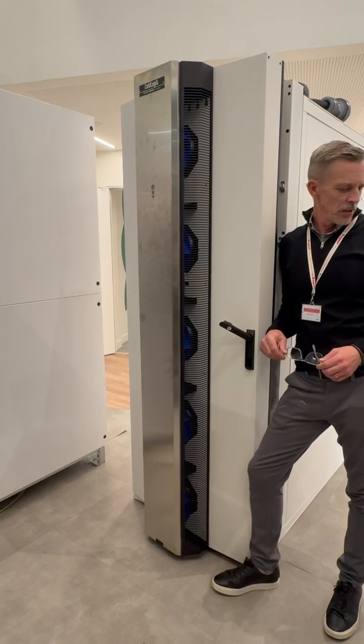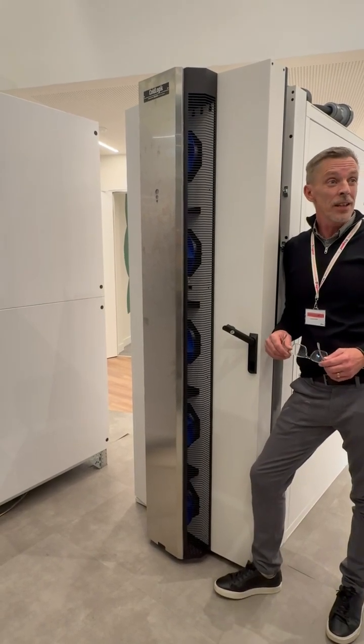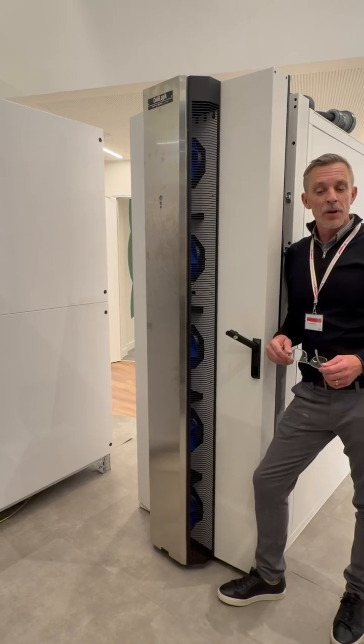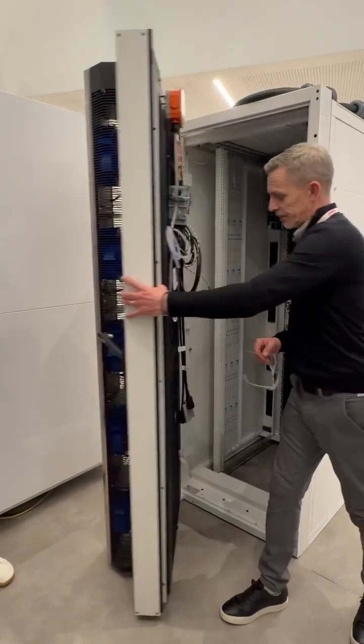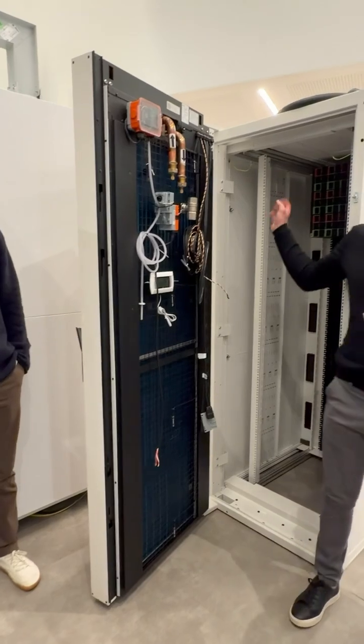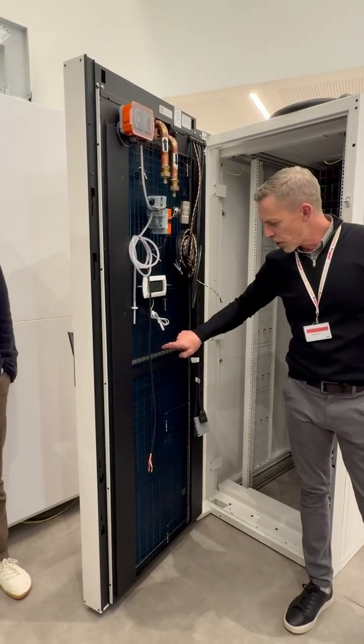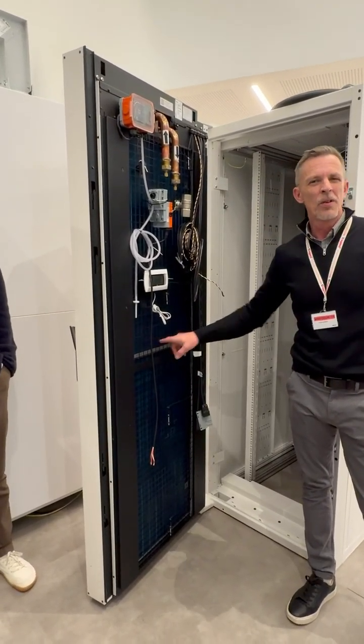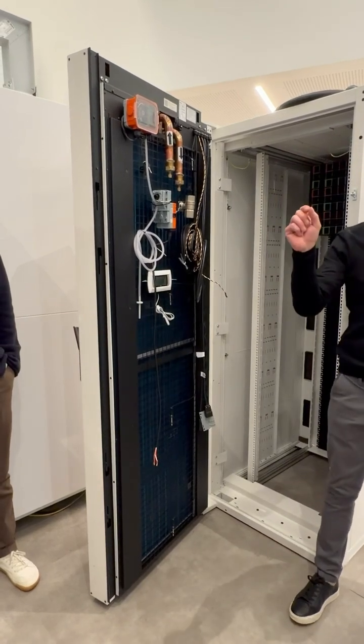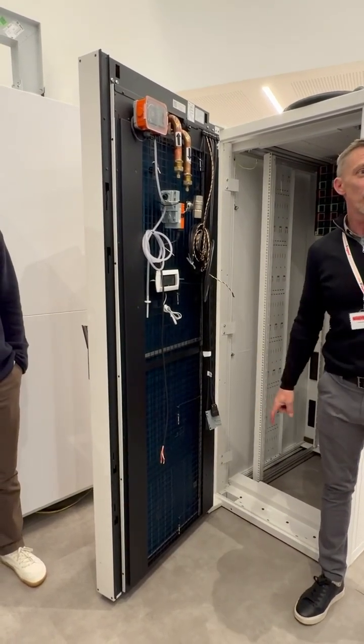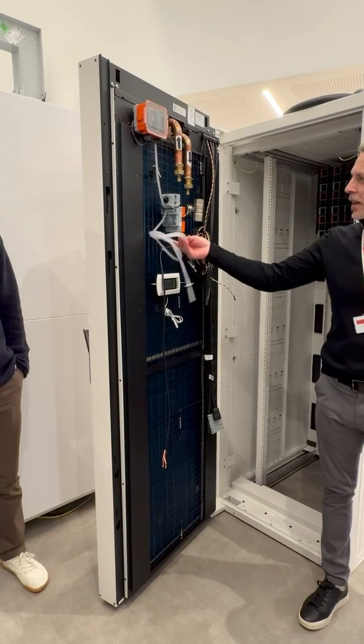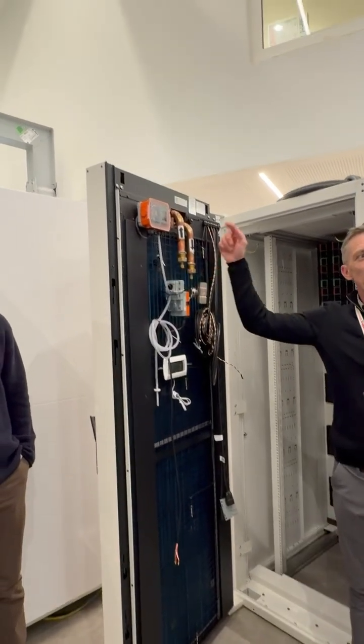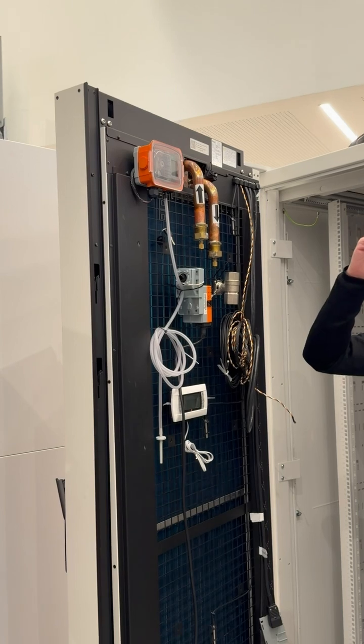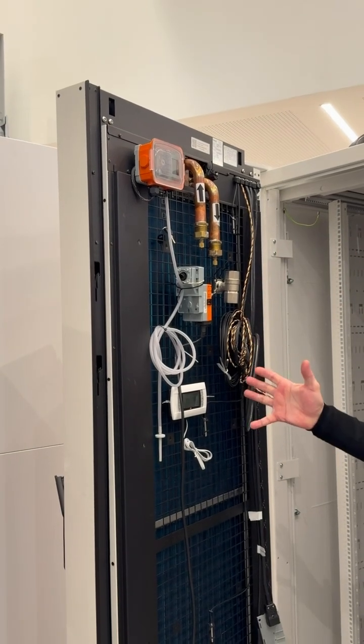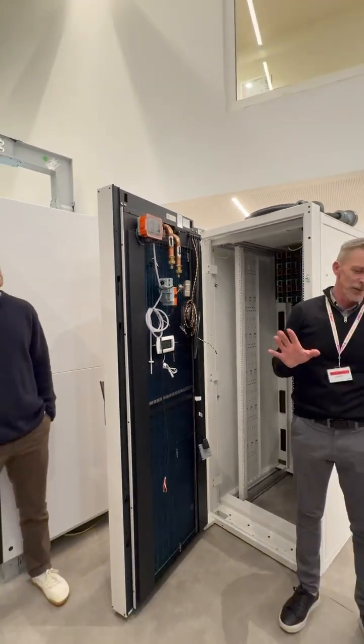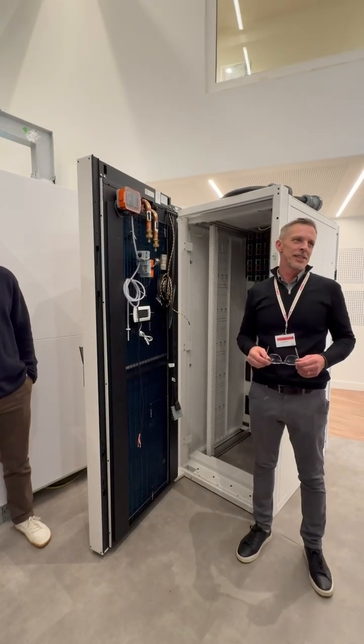What else did we have? Did we have anything else? Coils. Coils haven't failed. Coils have leaked where there would have been an incident. As an example, I've seen it where an engineer's been installing servers into there and they've bashed something and it's gone through and pierced the coil. It's a pinprick amount. They generally won't see any liquid, but what they will see, you'll see this, which is a pressure sensor. Back at the BMS, they see the pressure drop slowly in that rack, and then they go, what are we going to do? What we do, depending on who's done it, is under warranty. We'll replace the door.